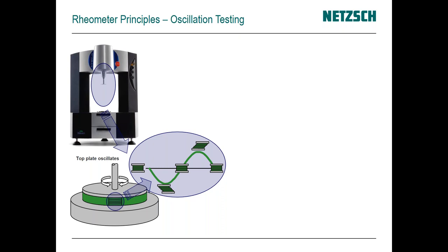When looking at deformation modes like oscillation, our goal is to oscillate the material and look at the forces generated. If we load a sample between the plates — the sample is the green area — as the upper plate oscillates back and forth, the sample goes from its loaded state to having its layers dragged in directions associated with the rotation of the plate.